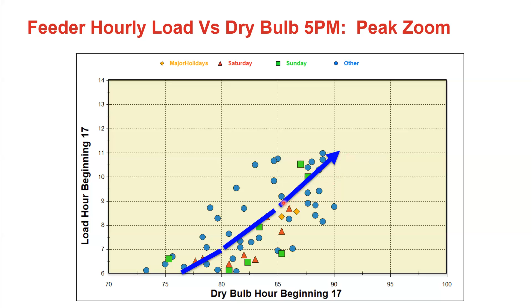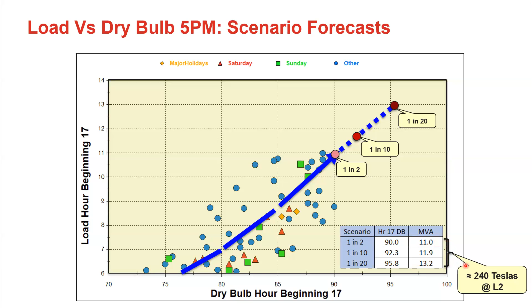Looking at the resulting peaks, 1-in-2 comes in at 11 MVA, and 1-in-20 is at 13.2. For context, where our model error was 10 Teslas at level 2, the jump from 1-in-2 to 1-in-20 on the circuit is equivalent to 240 Teslas being plugged in. So we want to make sure we're accurate when taking that jump, and this needs to be nailed down hourly because we'll see the peak shift as other DERs come online.